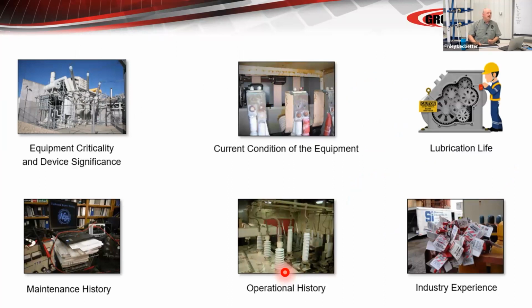Always take equipment criticality and device significance into consideration. Is it the main substation feeding your entire plant? Is it a breaker feeding a small section of your plant that has nothing critical in it? If they're the same breakers, maybe you need to swap them.